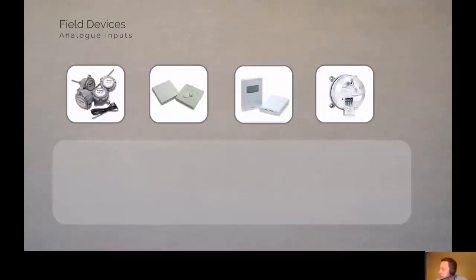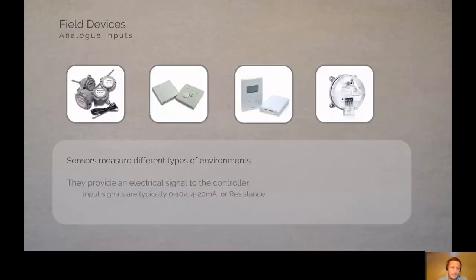We'll touch on analog first, but just as a simplistic note, the differences between analog and digital are quite simple. You've got digital, which is binary, or just on off, a 1 or a 0. And then you've got analog, which is a range of values, so anything between two different values. If we touch on the analog, analogs are anything: temperature, humidity, CO2, anything where you've got a number of values coming across, from which we can then take data from that sensor. In the case of temperature, it would be something like resistance or could be voltage, and then we'll convert that into a real world value for the BMS system that it can understand.